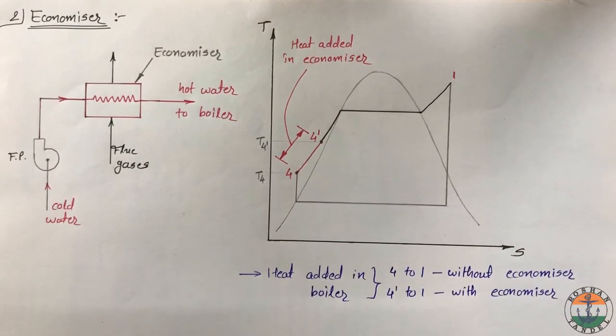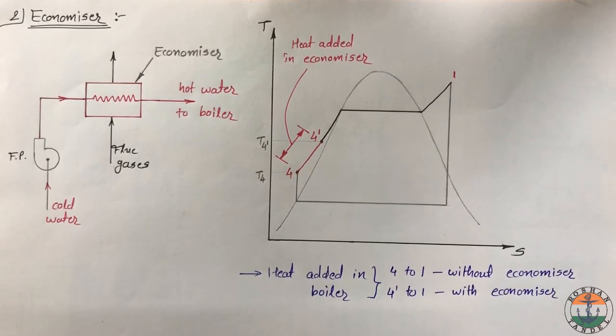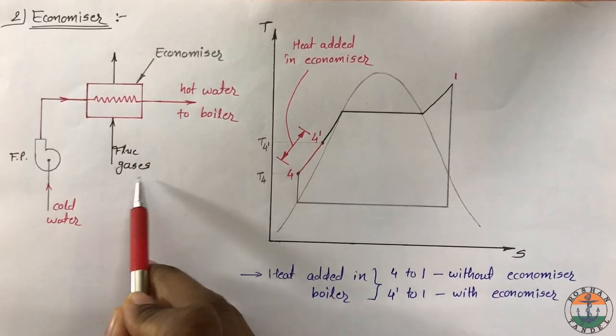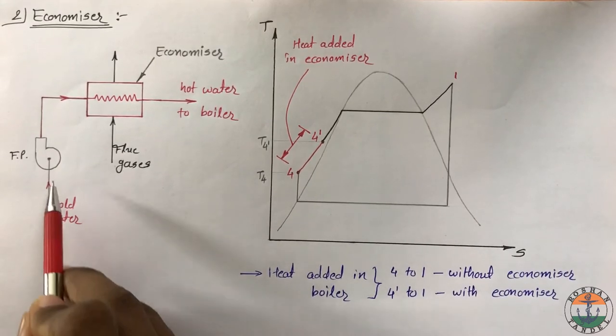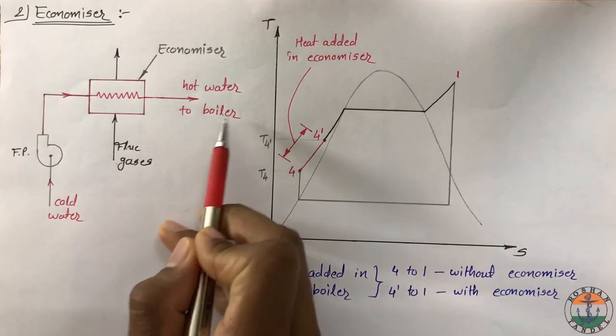The second boiler accessory is economizer. In a boiler, a lot of heat goes out to the atmosphere with flue gases. Economizer is a heat exchanger in which some of the heat of flue gases is recovered and is used to raise the temperature of feed water being supplied to the boiler.